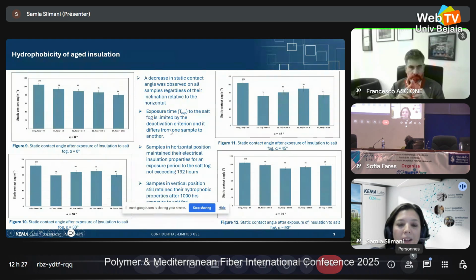I didn't explain before: the criterion is fixed to 2 milliamp during 2 seconds. So if the leakage current is above this value, the test is considered failed and stopped. As we can see from these pictures, the samples in a horizontal position maintain their electrical insulation properties for an exposure period to the salt fog not exceeding 192 hours. It's the maximum that they can resist without losing their hydrophobic properties.